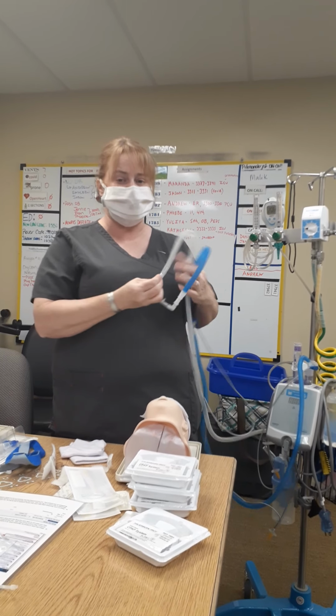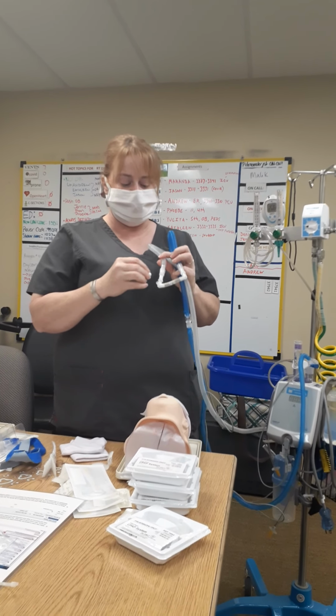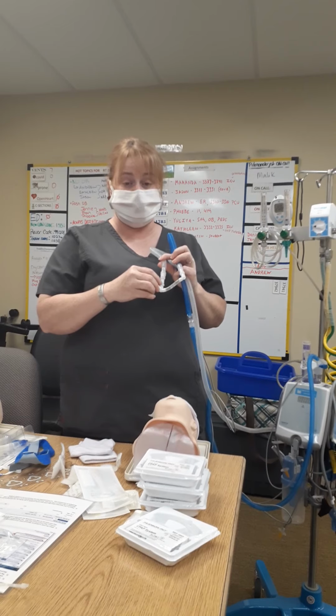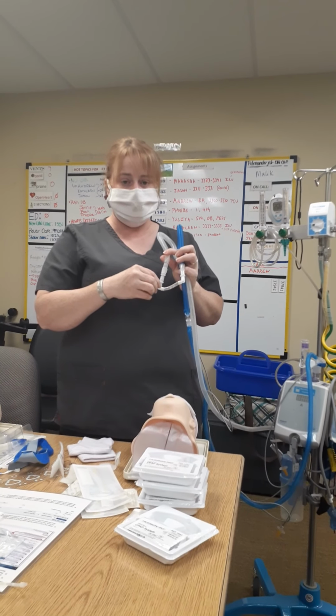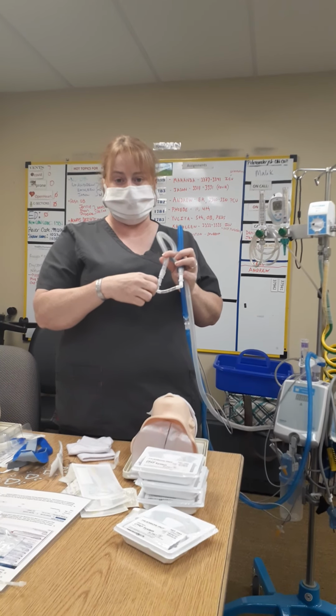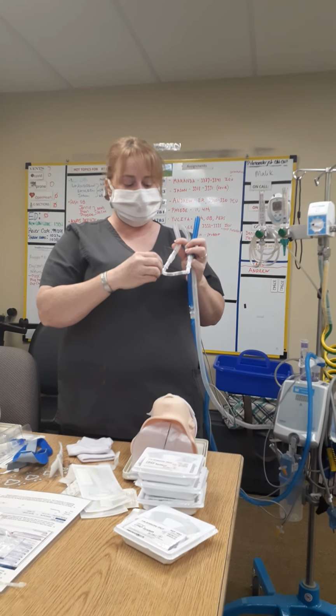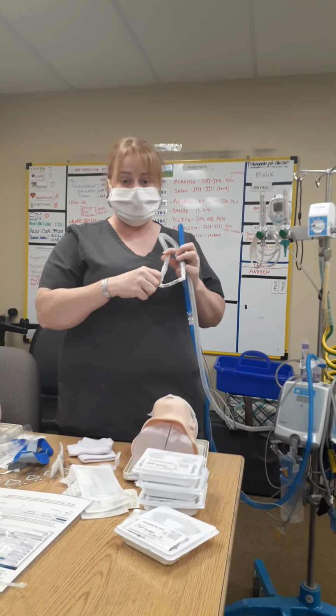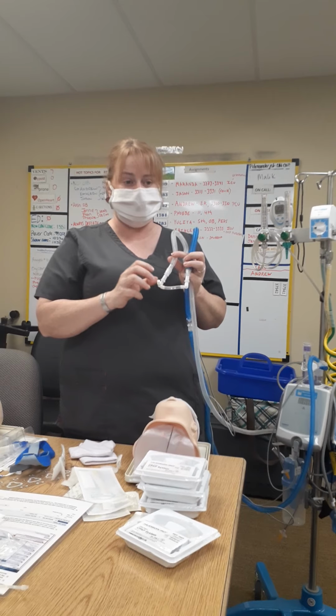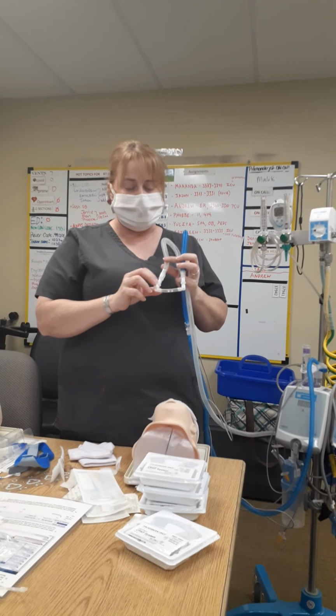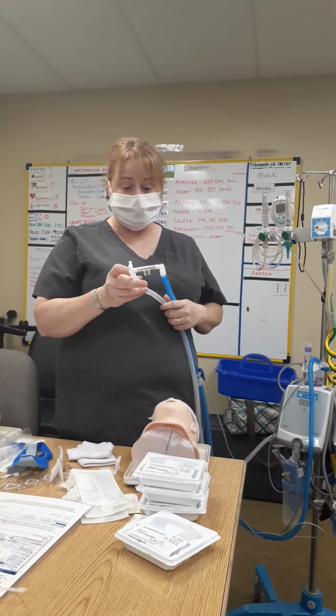This hole was actually designed to be where a pressure manometer could go. We're using a Luer lock, so you basically just screw it in and screw it out. Make sure that this hole stays plugged. This is not an exhalation port. This is a plug. And this is going to come in very handy very shortly.